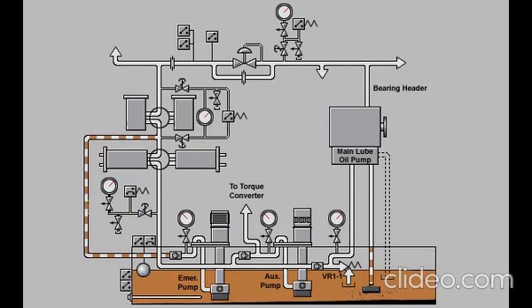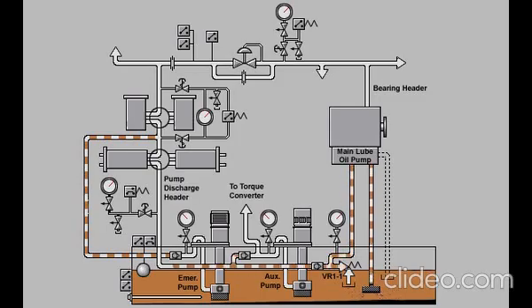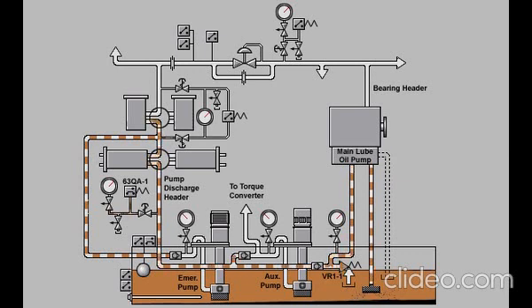With the gas turbine operating at 100% speed, lubricating oil is pumped from the lube oil tank by the main lube oil pump. As long as pressure in the pump discharge header is greater than 70 PSI, pressure switch 63QA-1 remains closed and the auxiliary lube oil pump remains in standby.